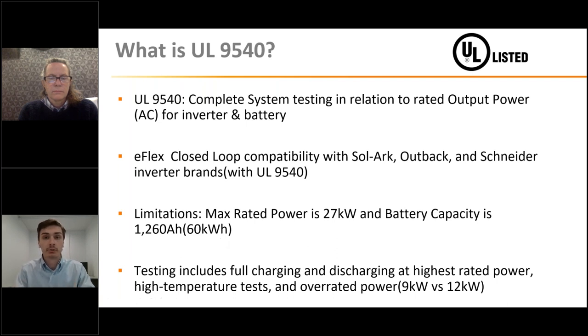Testing for UL9540 is extremely strenuous, as it includes full charging and discharging at the highest rated power of the inverter and battery, high temperature tests to see how the BMS responds and functions, and overrated power testing—for example, a 9 kW inverter versus a 12 kW inverter, and how it responds to different currents from larger versus smaller inverters.